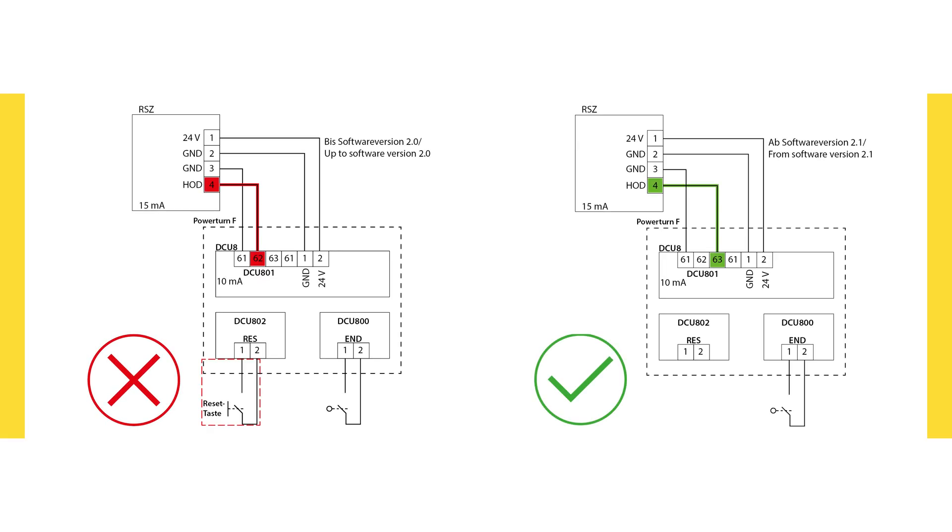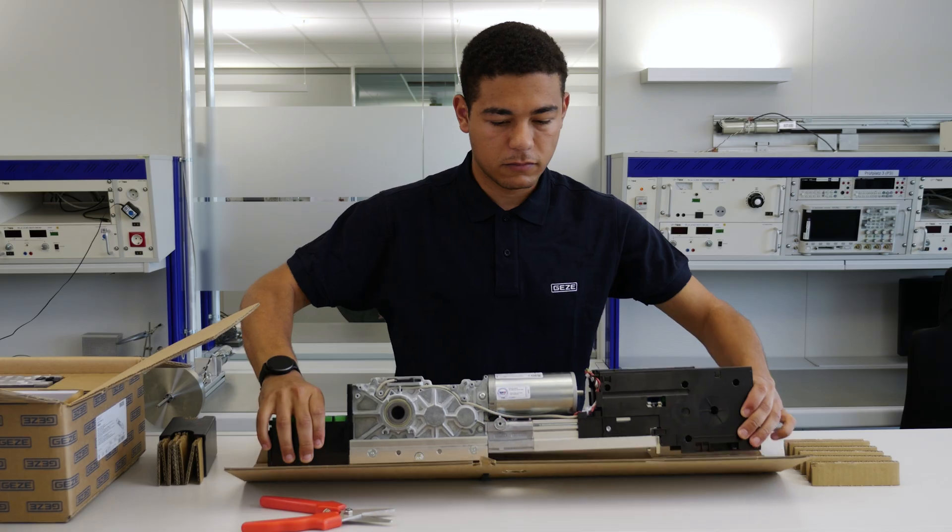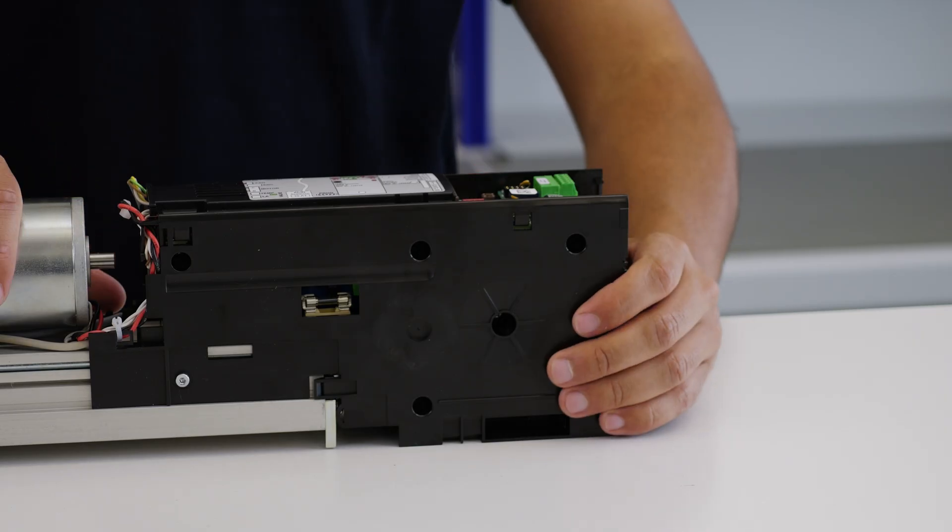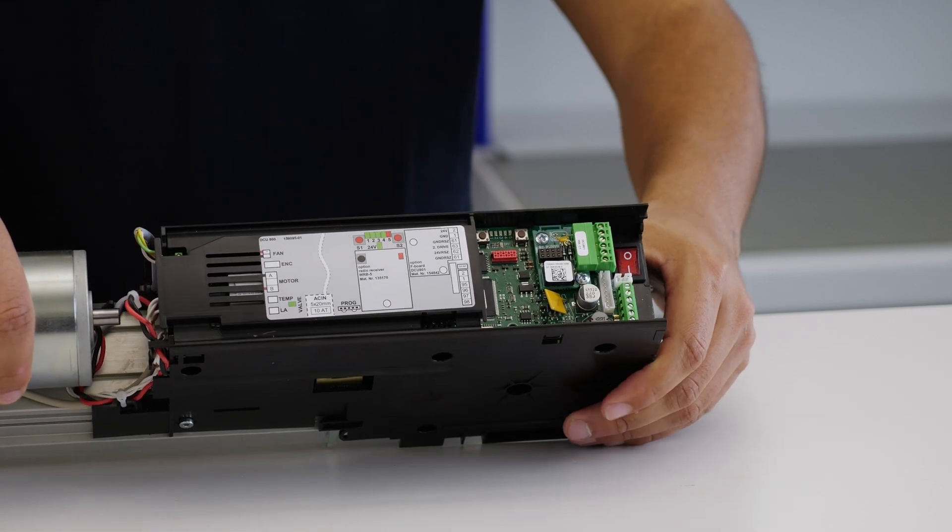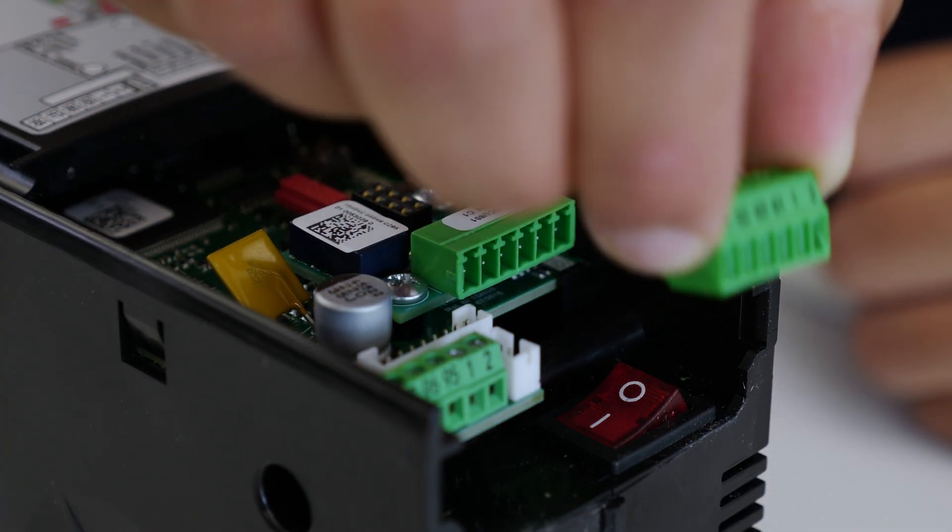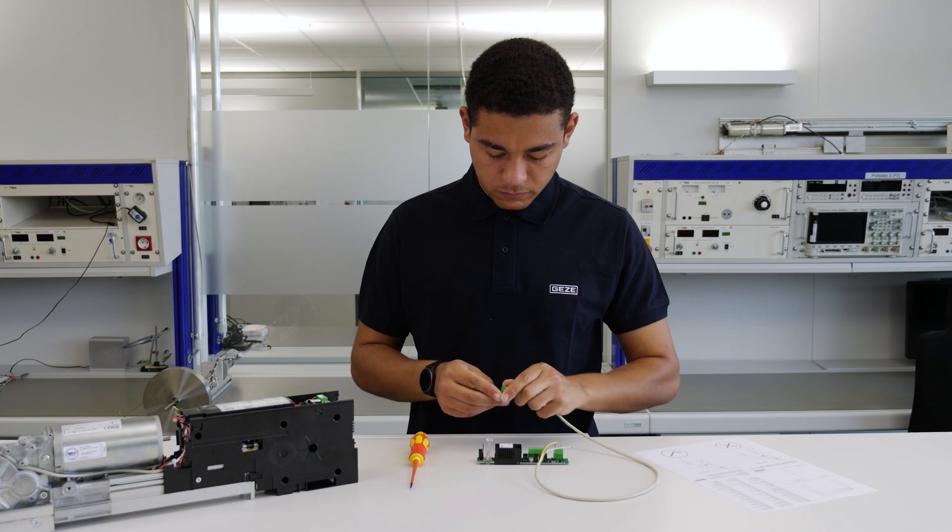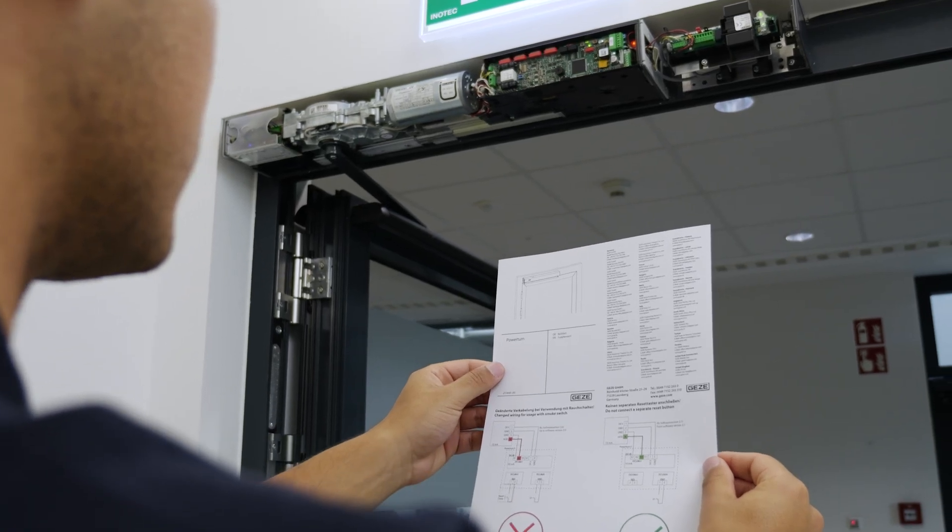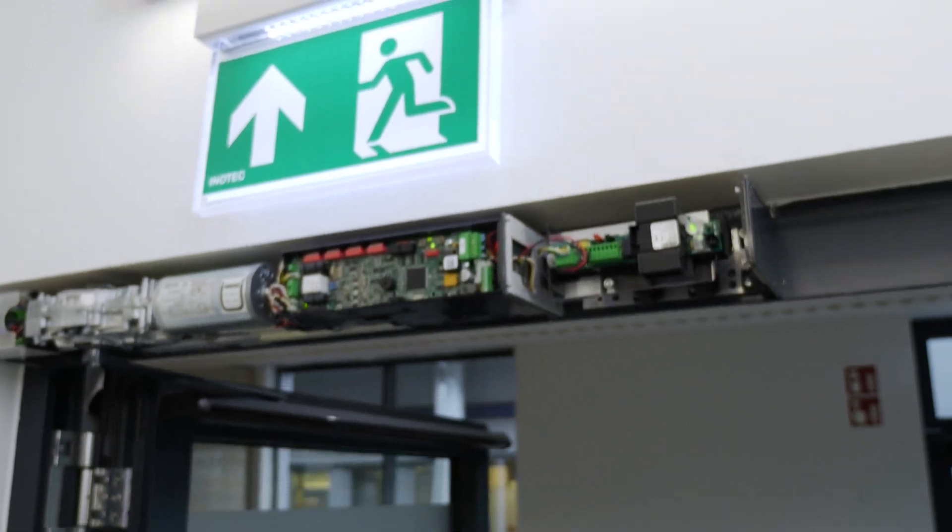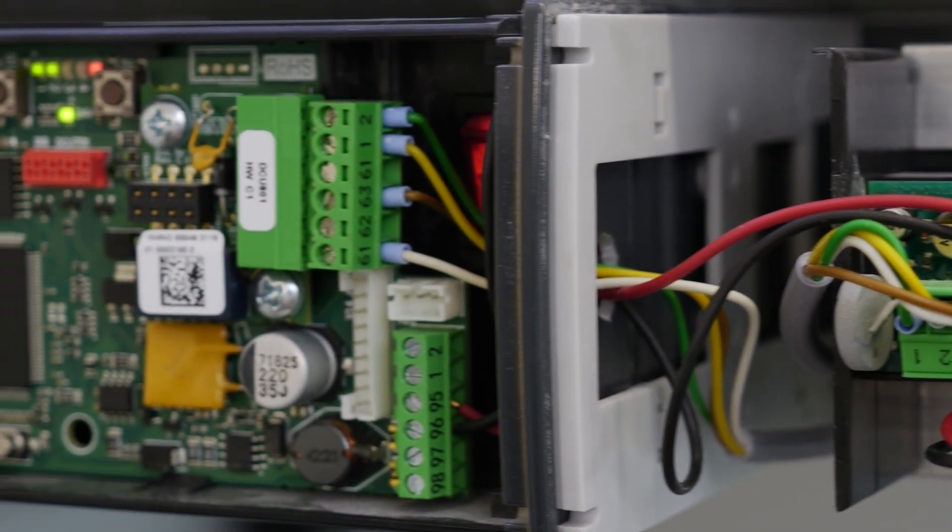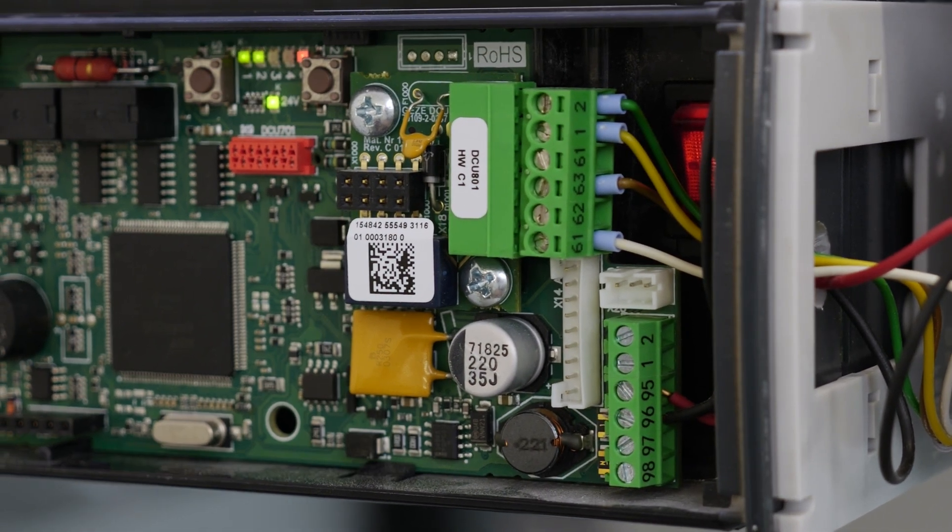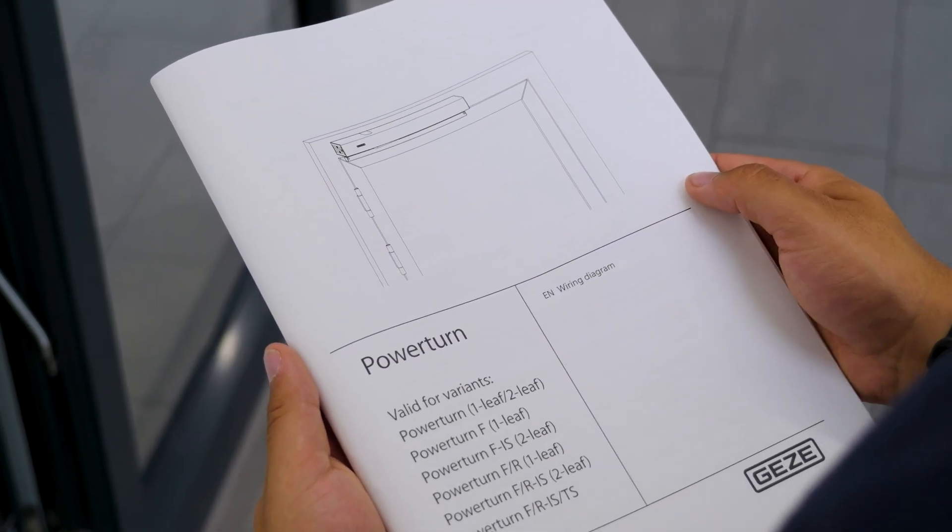Previously, the GC151 smoke switch was connected to terminal 62 on the Power Turn. From now on, it must be wired to terminal 63. To do this, use the terminal block on the DCU 801 F board. Wire the individual wires of the smoke switch to terminals 1, 2, 61, and 63.